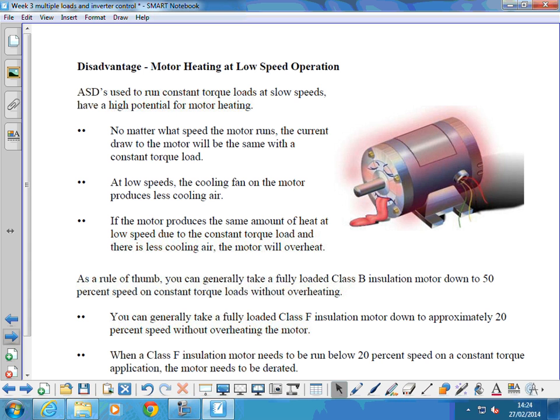If the motor produces the same amount of heat at low speed due to the constant torque, then the less cooling air will mean the motor will overheat. As a rule of thumb, you can generally take a fully loaded Class B insulation motor down to 50% of its rated speed on constant torque loads without overheating. The issue's not there so much if your torque is going to reduce when you reduce speed, because then it's not going to get so hot anyway. It's going to be drawing a lower current. You can generally take a fully loaded Class F insulation motor down to 20% of its rated speed without overheating.